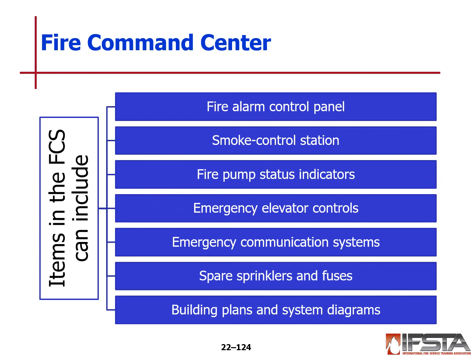In your fire command center, you'll find items such as the alarm panel and smoke control stations. It may be able to control fans, pressurize certain areas, and turn off fans or air handlers, or have control of the HVAC system, if you will. Fire pump status and indicators: if the building and system are equipped with fire pumps, are they running, and which ones are running if it has multiple pumps.